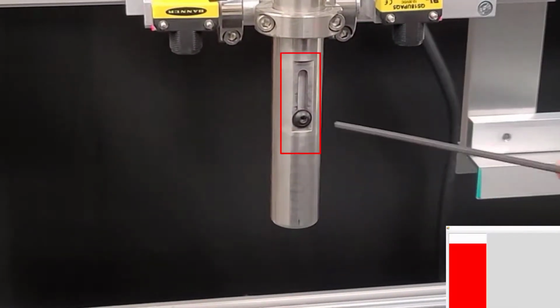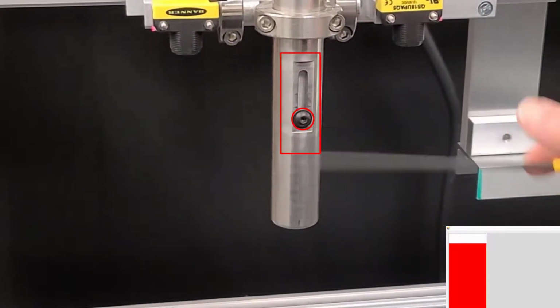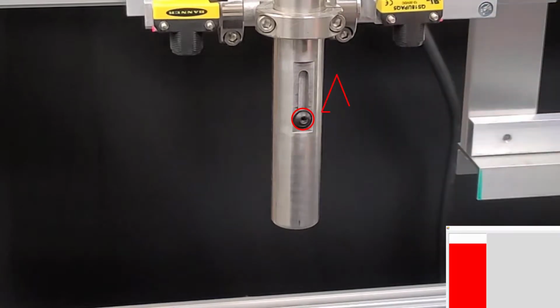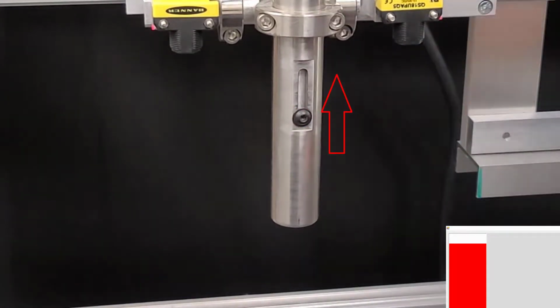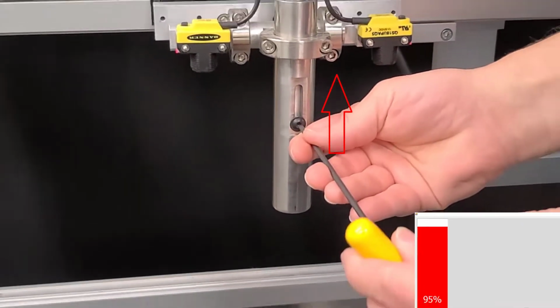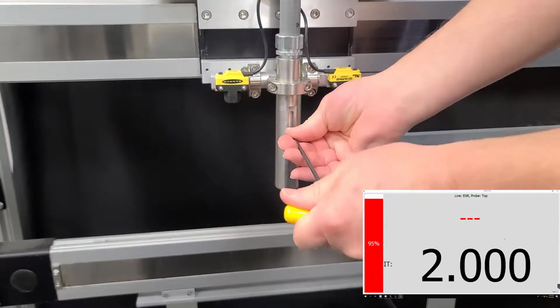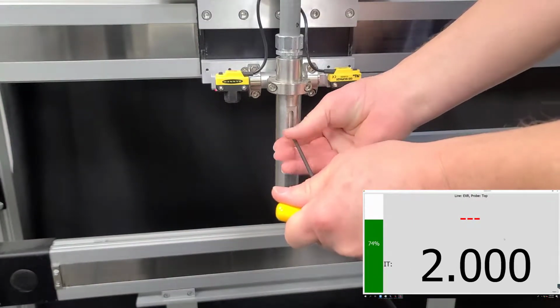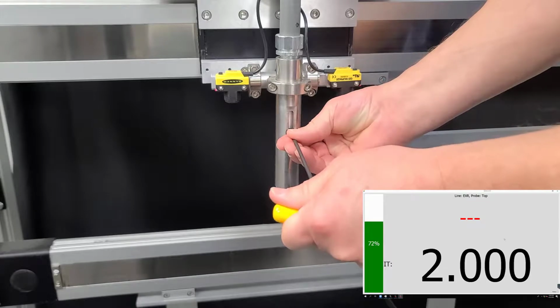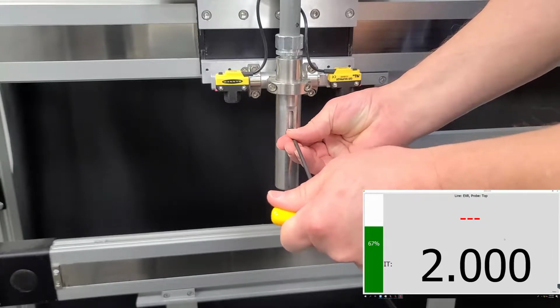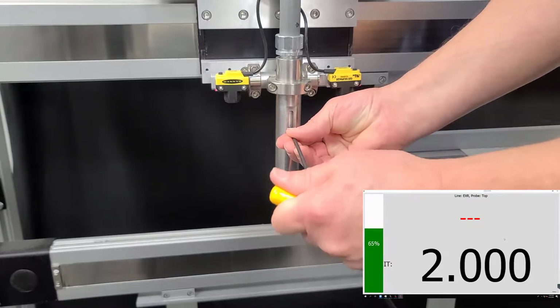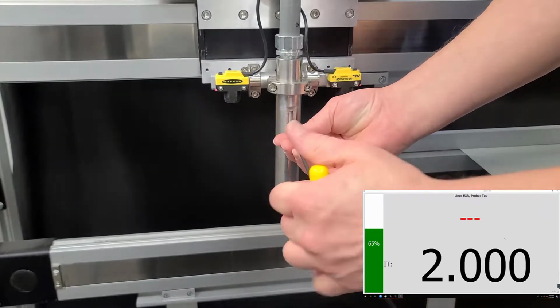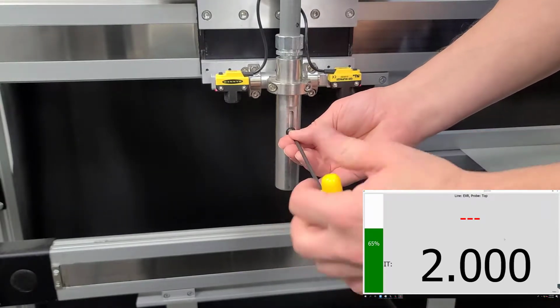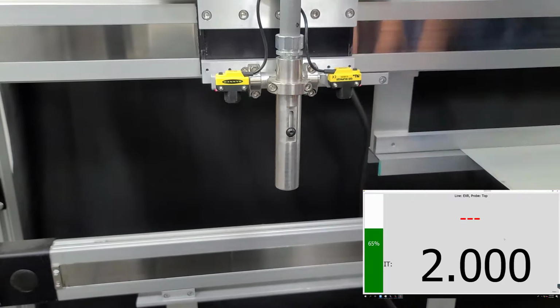Using the 1/8" SAE hex, slightly unscrew the probe focus adjustment and begin moving the adjustment away from the tip of the probe. As you adjust, you should see the reflectance percentage decreasing. The bars should turn green around 80 to 85%. However, you want to continue decreasing reflectance until you reach 65% for the EXR spectrometer types. Tighten up the hex once it's completed, and you're done.